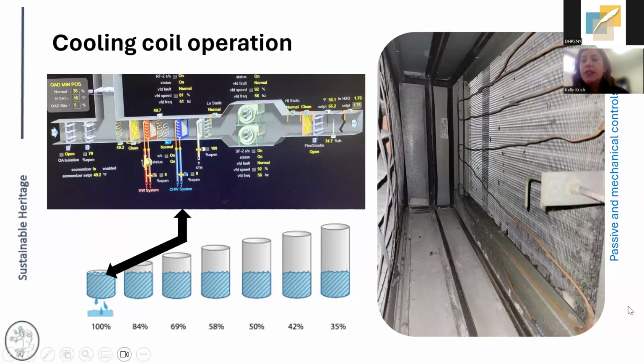And you can see on the right what it looks like in real life. So there's your coil with the water running, cooling that pipe. The air is going to pass over it, and, again, I hope you can see my arrow, the moisture is going to condense out and go through that piping back to the drain. So the cooling coil here is the component that gets our bucket small enough that we're removing moisture. And so in many systems, this is the primary way that we can dehumidify and remove moisture. Otherwise, increasing temperatures or things like that is not actually changing the total moisture that we have within a space.